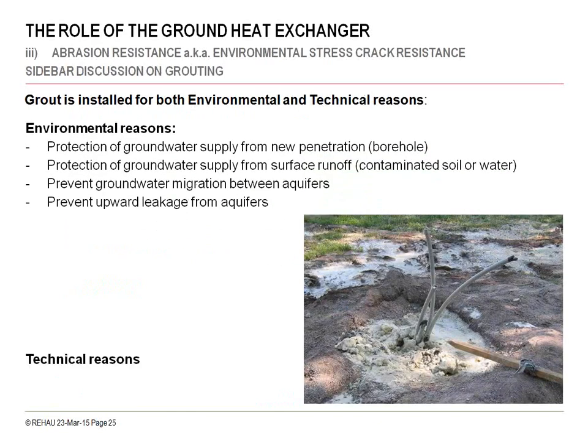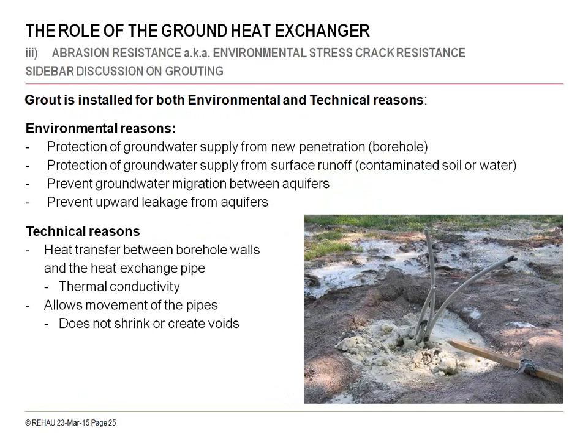Grout is used on vertical boreholes, and the two main reasons for grout would be environmental and technical. On environmental, we're using a bentonite clay that aids in sealing the borehole from the bottom all the way to the top to prevent surface contaminants getting down into the groundwater, into the aquifer. The technical reason for utilizing grout would be to enhance the conductivity of that borehole.